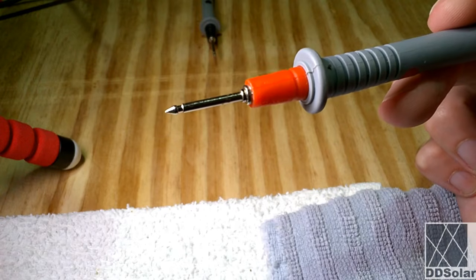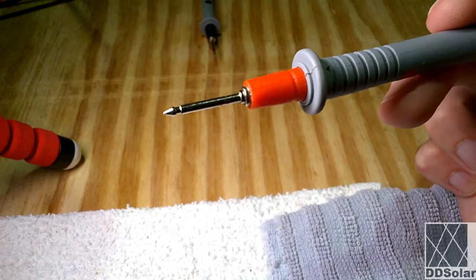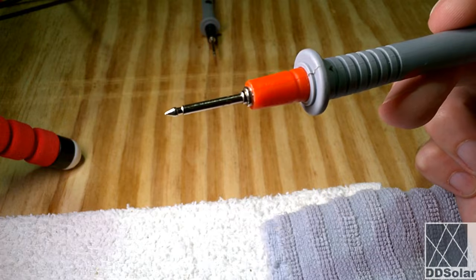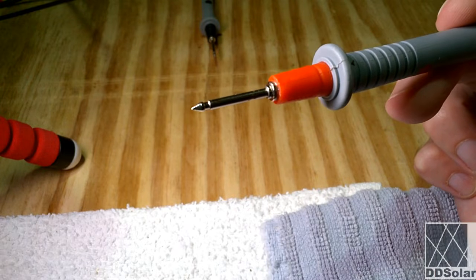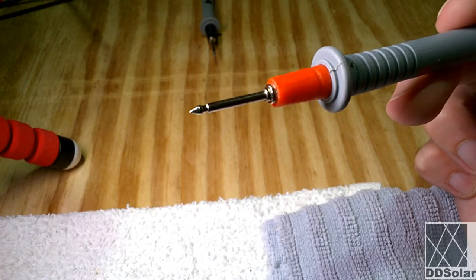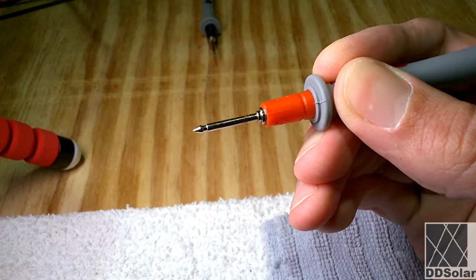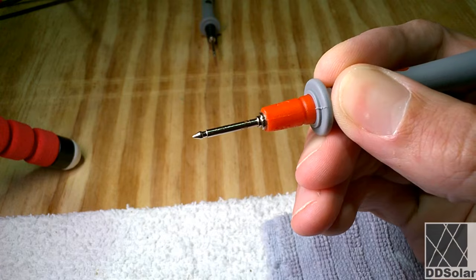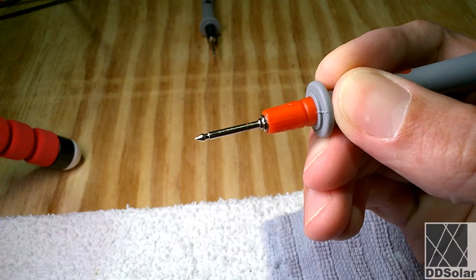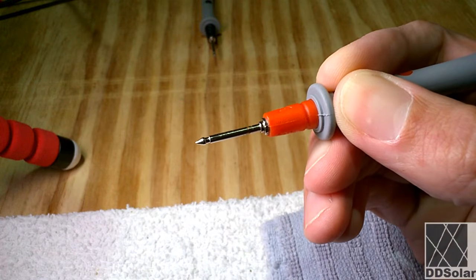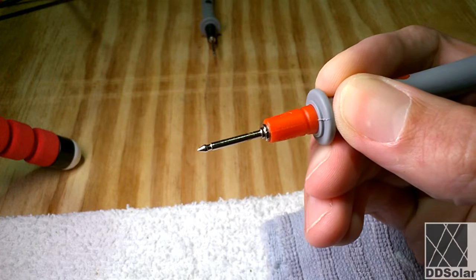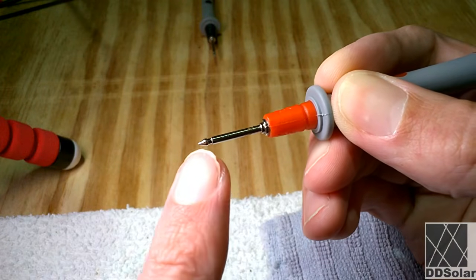Sometimes there will be some oxidation or corrosion on a measuring location, and by taking this probe and scratching with the sharp end, you can actually get a good connection and take a voltage or a resistance measurement. Near the end of the probe, you can see where my fingers are. There's a finger guard, and generally speaking, you're not supposed to put your fingers past that line. That's to protect your hands from slipping and making contact with the metal part of the probe.